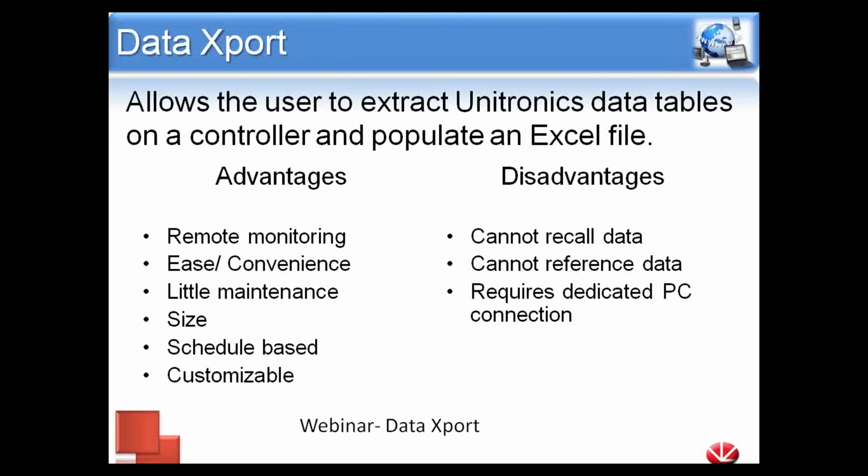Size is a very big advantage to data export. We are, of course, limited to the size of the data tables on the controller. However, we can set up a schedule to call these data tables back to your PC, populate the Excel file, and then clear the table. So really, we're limited to the amount of space you have on your PC.